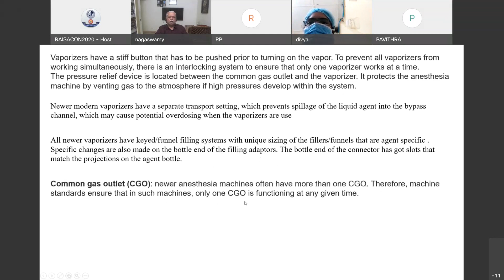And then come the common gas outlets. In the newer machines, they have more than one common gas outlet. Therefore, machine standards ensure that such machines function through only one at any given time. So if you are going for a newer machine, you have to check for that. And scavenging systems all have 30 mm diameter connections. Normally in the machines, we have only 15 and 22 mm. So to avoid a misconnection, all the scavenging system connectors are 30 mm connectors, and there are negative and positive pressure relief valves incorporated in the scavenging systems.